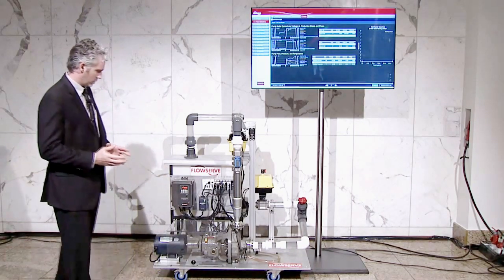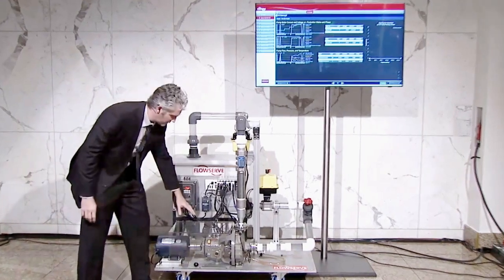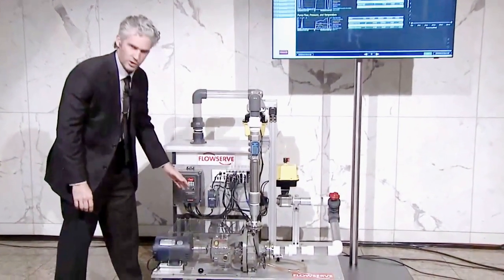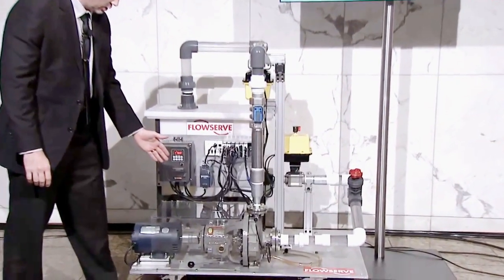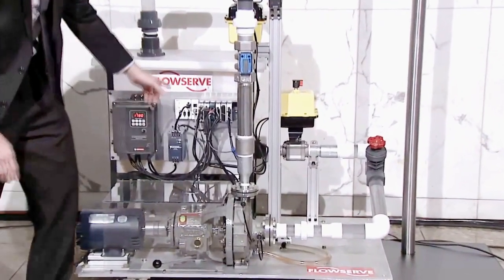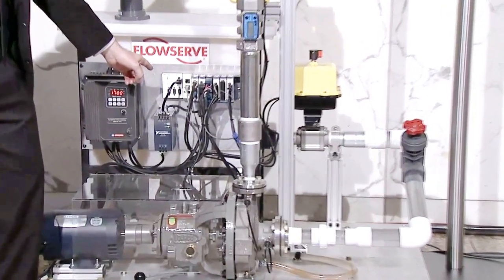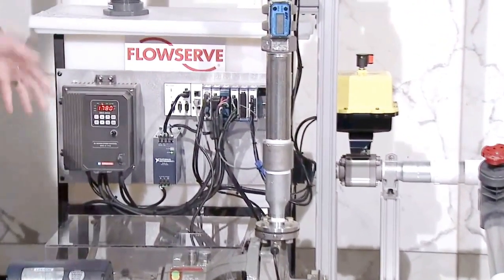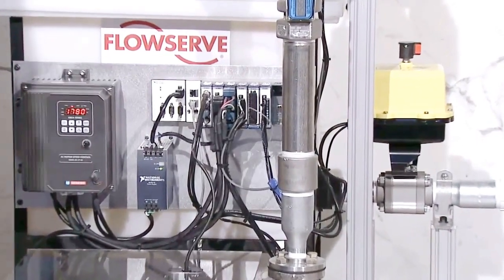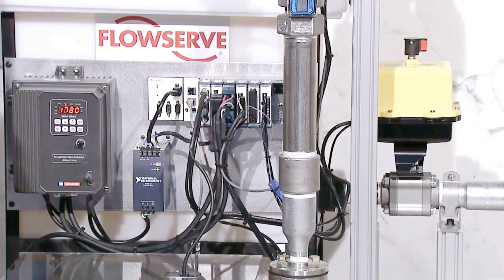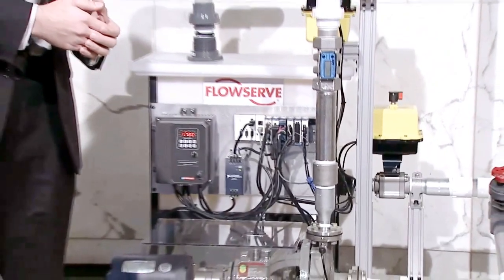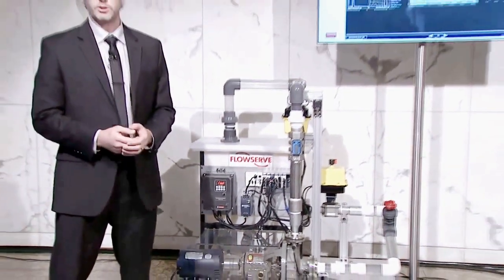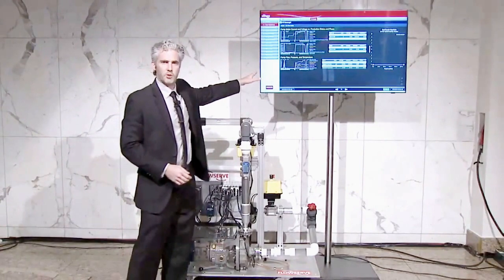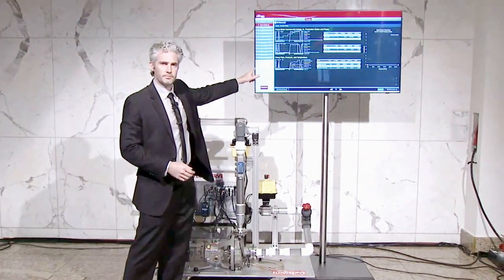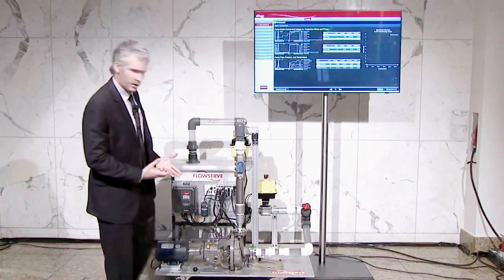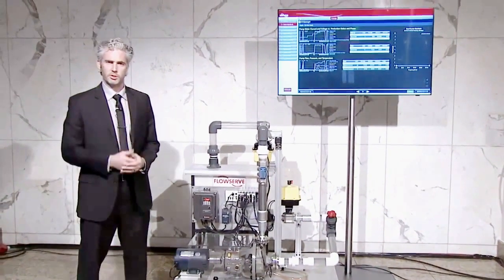So the way that the system works is, first of all, we've instrumented this pump with a lot of different sensors like pressure, temperature, vibration, flow, and power measurements. And all of those measurements are being made by our National Instruments CompactRIO data acquisition system here. Now, thanks to the collaboration between National Instruments and OSIsoft, we can send this data in real time from our InsightCM software or our LabVIEW software directly to the PI system for real-time data tracking, which is what we're showing here on this screen.